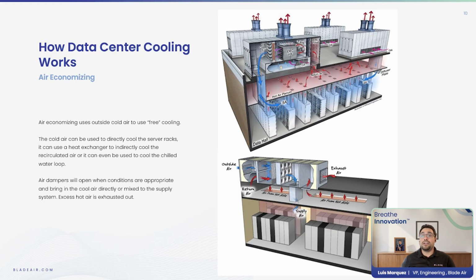Finally, we can talk about air economizing. Air economizing works by bringing in free cool air to cool down the racks. Similar to evaporative cooling, it can be used direct or indirect. So it can be brought in to cool the racks and hot air directly, or to help the chilled water loop. It's very simple. It just works by having air dampers open when outside conditions are appropriate, and they bring in cool air while excess hot air is exhausted out, as you can see in the examples.